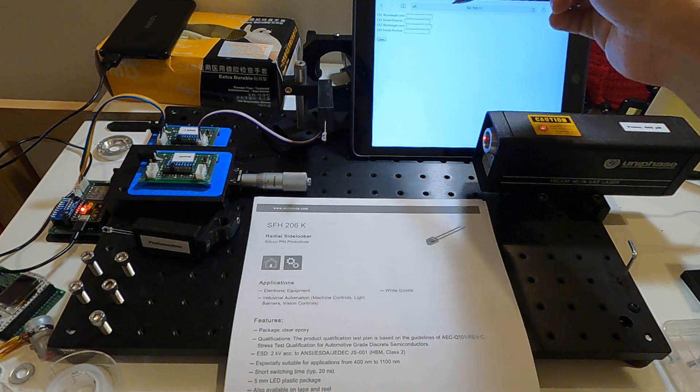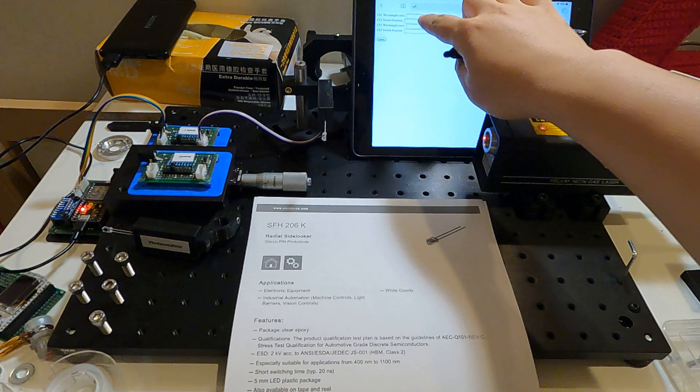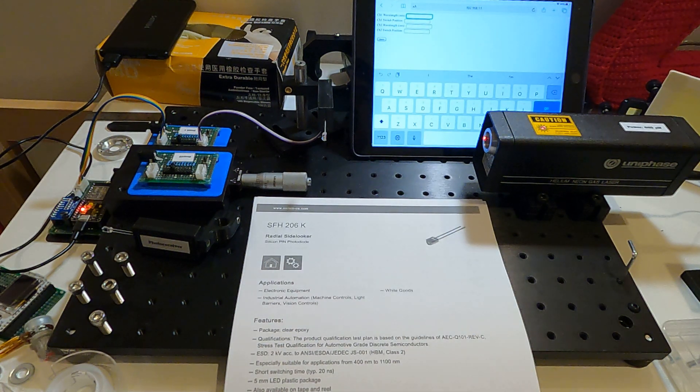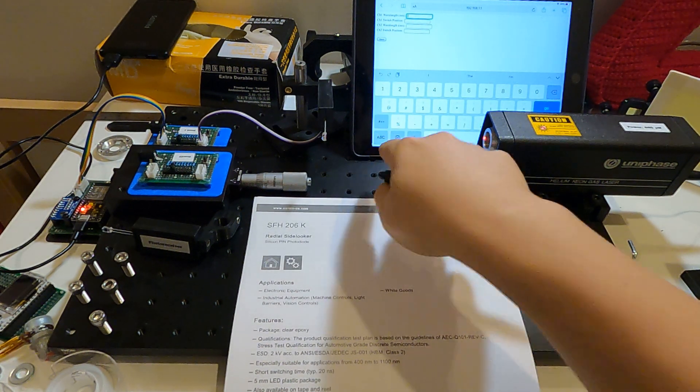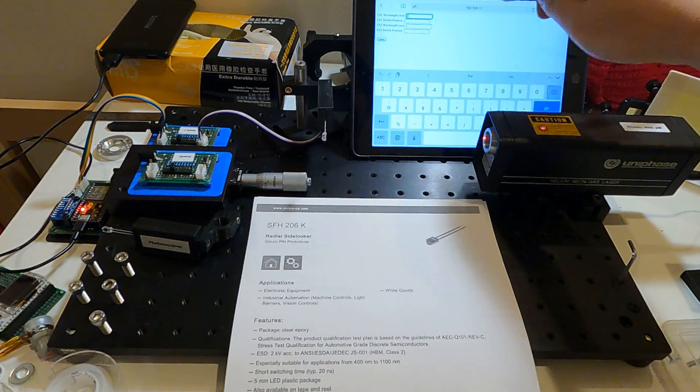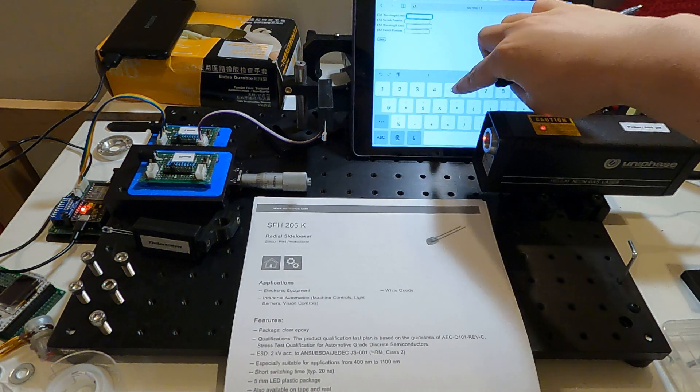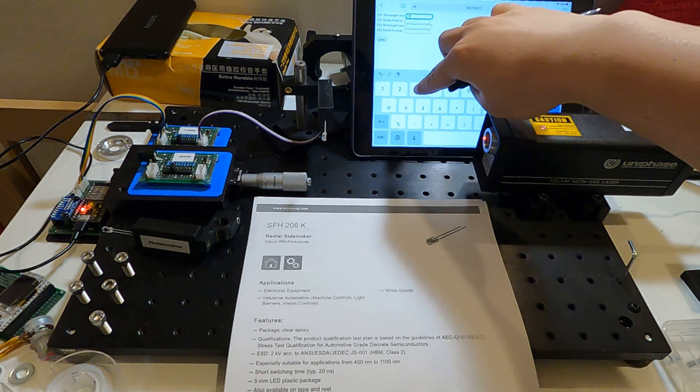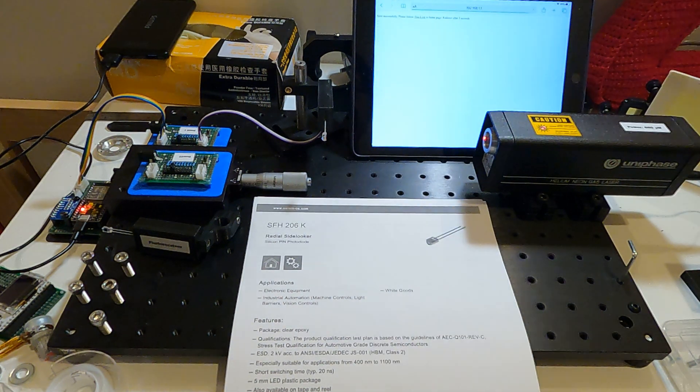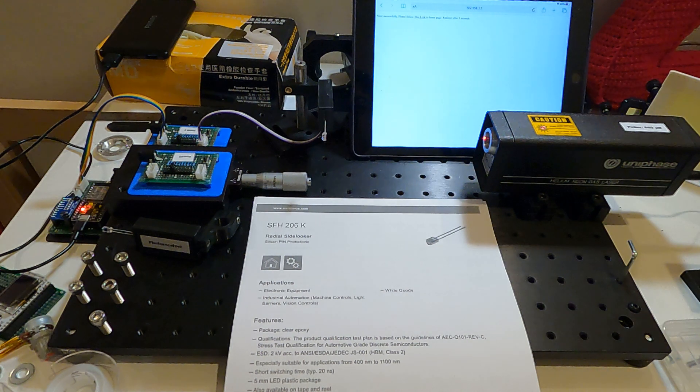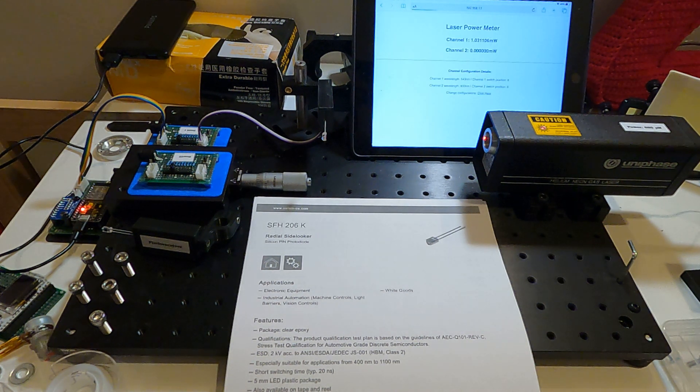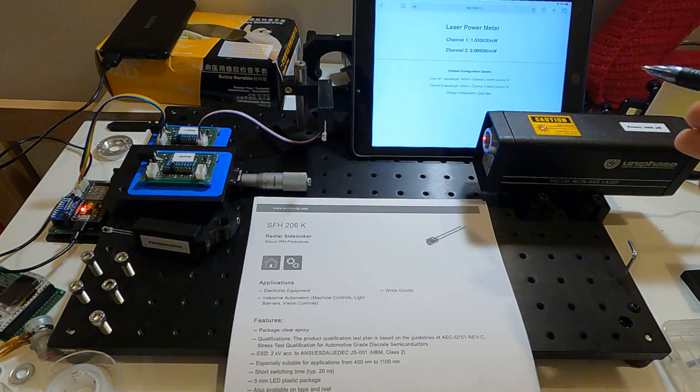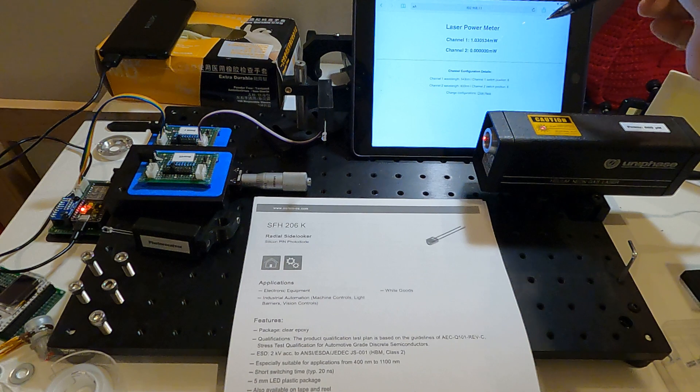For example, if we want to measure a green laser, we can change the wavelength to 543 nanometers and click save. After 3 seconds it will go back to the home page and you can see the value changes in channel 1.